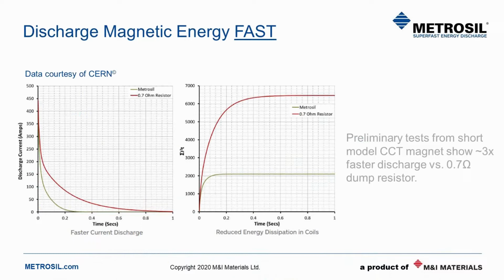Here you can see the METROSIL go up against a 0.7 ohm linear dump resistor during a quench. Not only is the current discharged a lot faster, but the sum of the I squared T's, representative of the energy discharged within the coil, is a lot lower when a METROSIL is used.